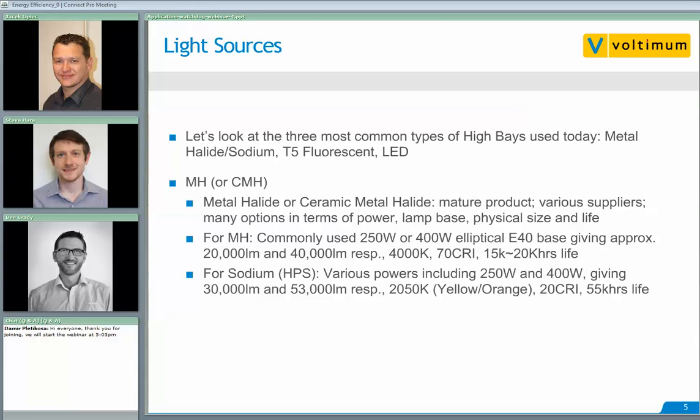The 250W and 400W metal halide lamps give approximately 20,000 lumens and 40,000 lumens respectively for the bare lamp. You can get them in 4,000K, 70 CRI, and they have a lifetime of about 15,000 to 20,000 hours before failure. For high pressure sodium, 250-watt and 400-watt versions give 30,000 or 53,000 lumens respectively — quite a bit higher than metal halide. However, the color temperature is about 2,050 Kelvin, giving a very yellow or orange hue with a very low CRI of 20, though it has a very long lifetime of about 55,000 hours.